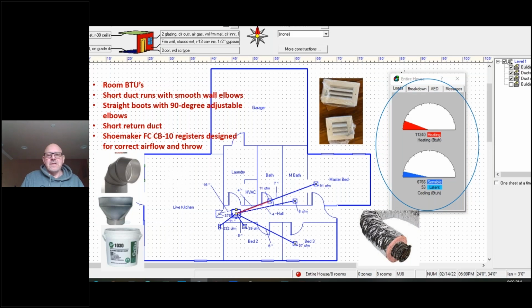So we also use straight boots, which is here on the left. We don't want any kind of friction, so we put a 90-degree elbow right on top of it. Anytime we're turning around or doing a U-turn, we're using multiple smooth-wall 90s, so this flexible ductwork doesn't kink. Then everything in between is this flexible ductwork on the right here. And then we use a lot of mastic. Mastic is our best friend. Use lots and lots of this. It's becoming very expensive, but we still use a lot of it.